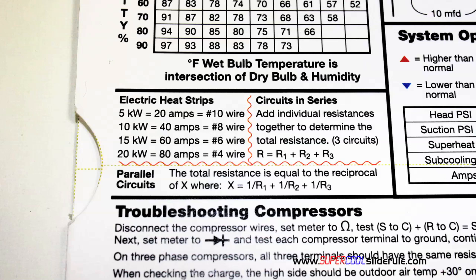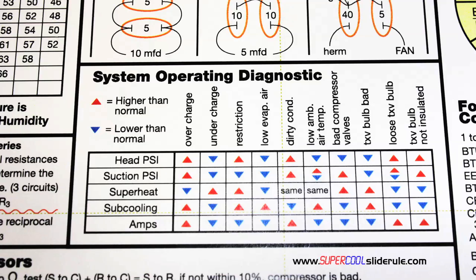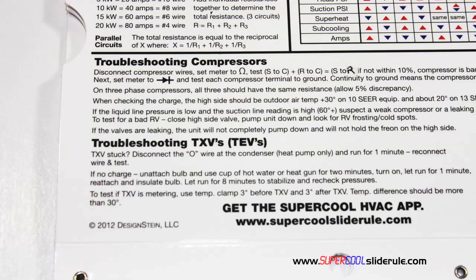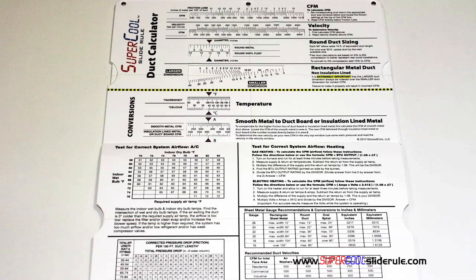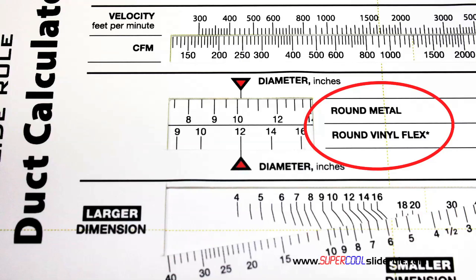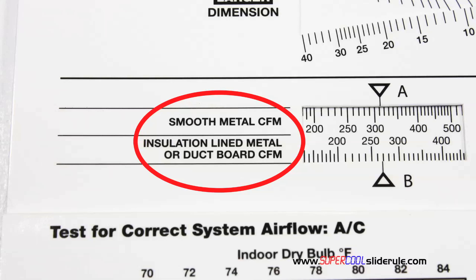It includes an electric heat strip guide, a complete system troubleshooting diagnostic chart, and how to troubleshoot compressors and TXV. Inside is packed with even more information. It performs sizing of both metal and flexible duct, and has the only direct reading conversion from smooth metal to insulation-lined metal we've ever seen. Most technicians have never been taught that if the insulation is on the inside of the ductwork, you cannot size it with a regular duct calculator.